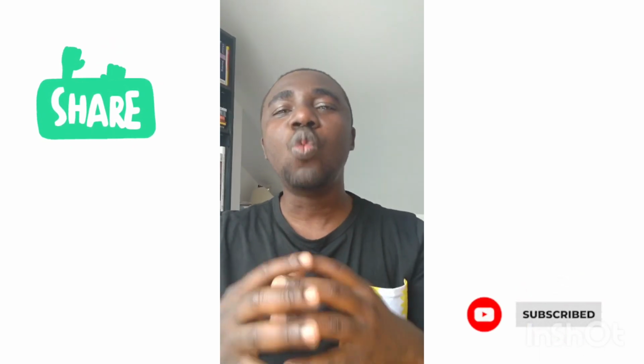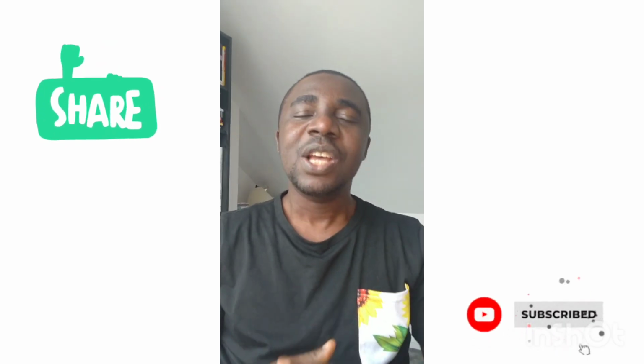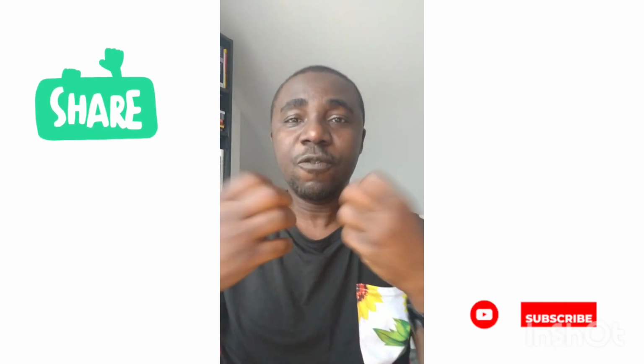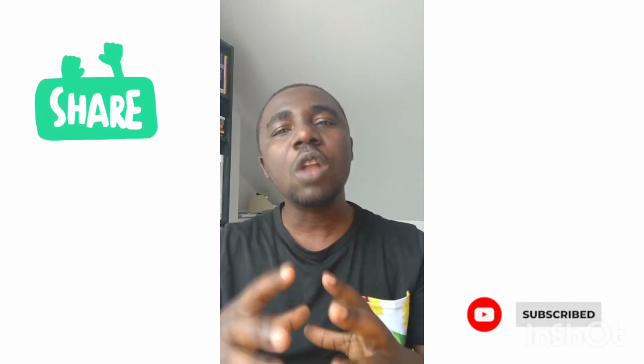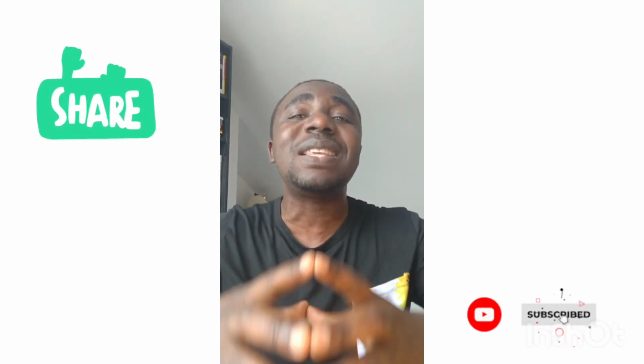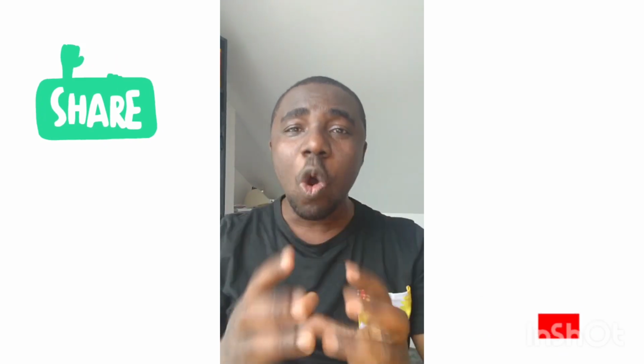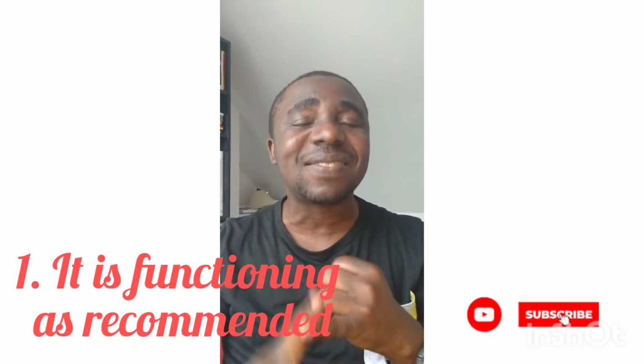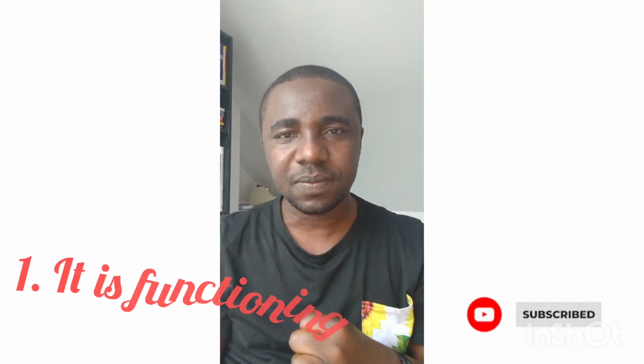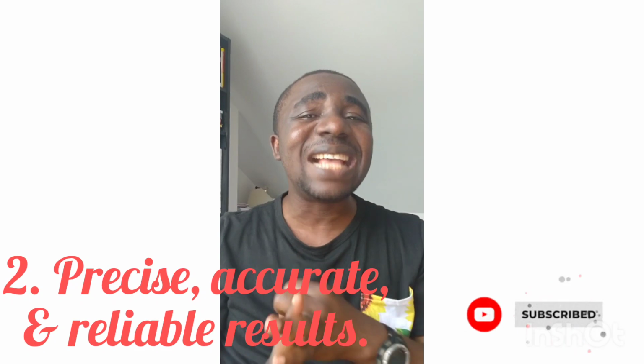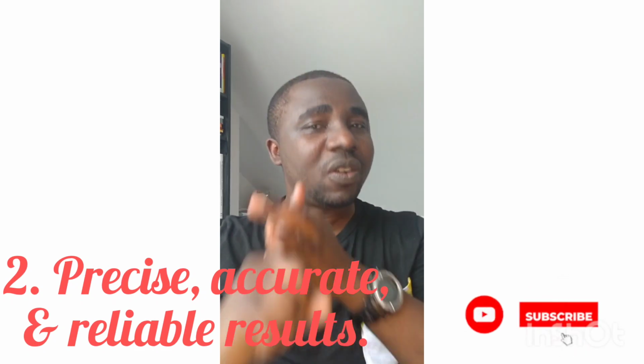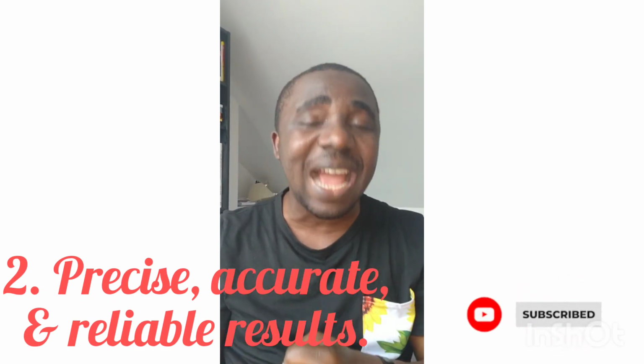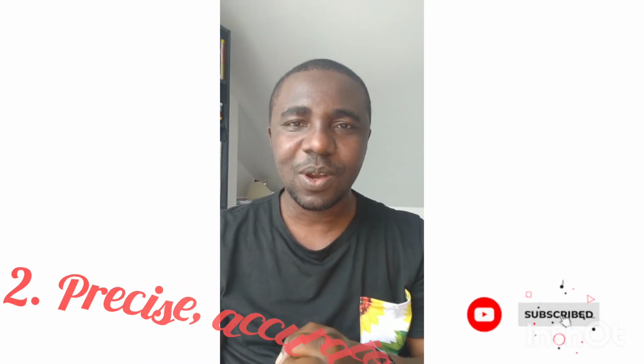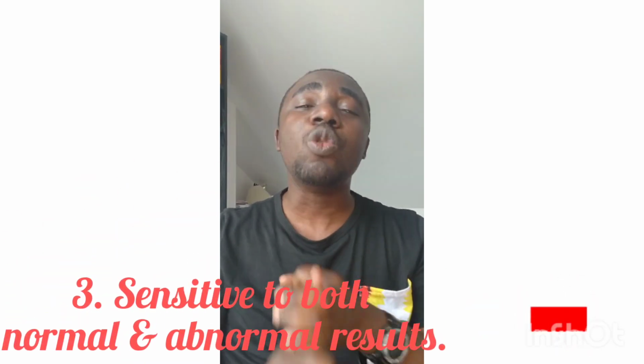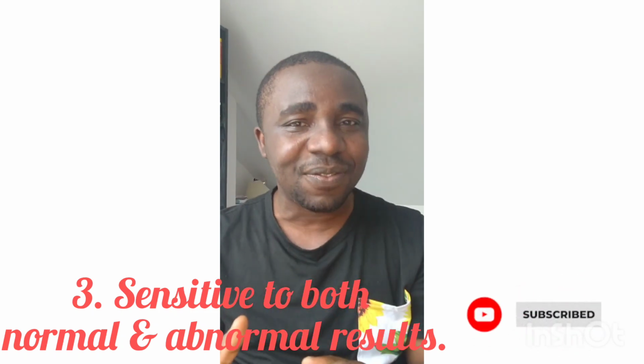Now, what is analyzer validation? You have this new analyzer that you've bought - how can you validate it? You are going to validate that analyzer by doing a lot of things. What it generally means is that you want to test that analyzer to make sure, one, it is functioning as recommended by the manufacturers. Two, that analyzer is going to be giving you good results - that the result will be precise and also accurate. Three, you also want to make sure that analyzer is sensitive.